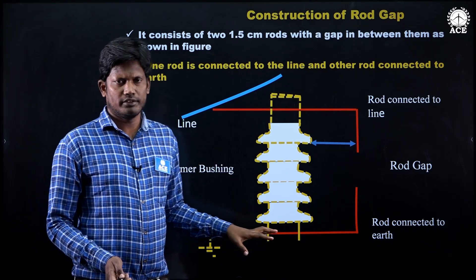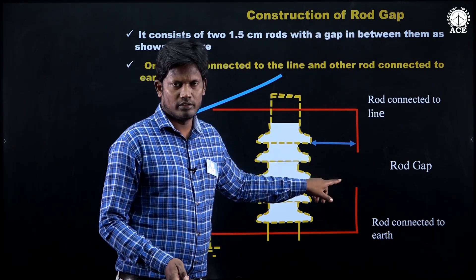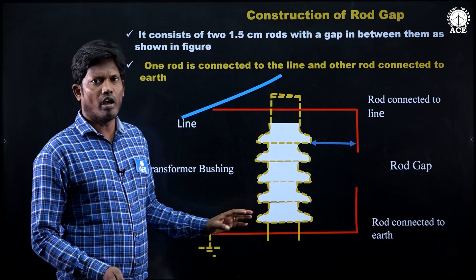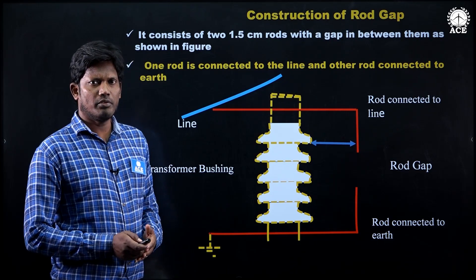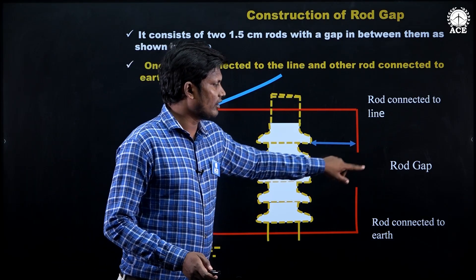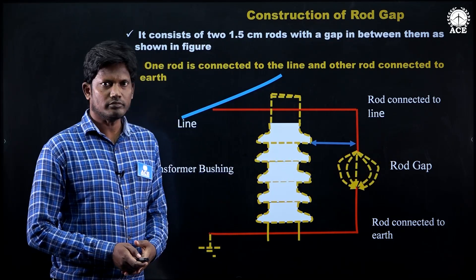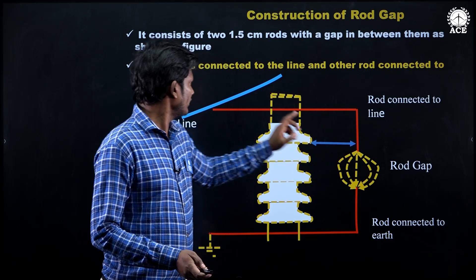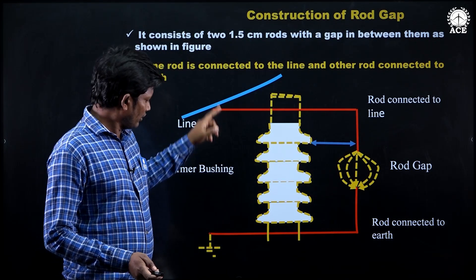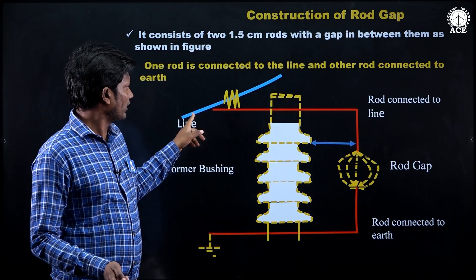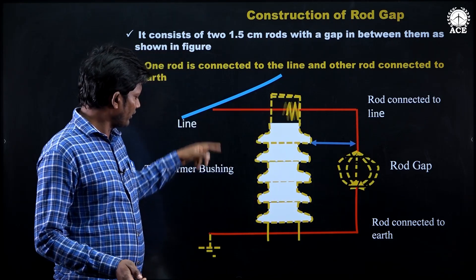Under normal condition, the gap is non-conducting because normal voltage is not able to break the air insulation between the gap, so no arc is formed. But high voltage breaks the air insulation between the gap and arc is formed as shown in the figure. When the arc has formed, the gap is conducting, and it conducts the high voltage from the line to ground through the rod gap. This high voltage diverts from line to ground.